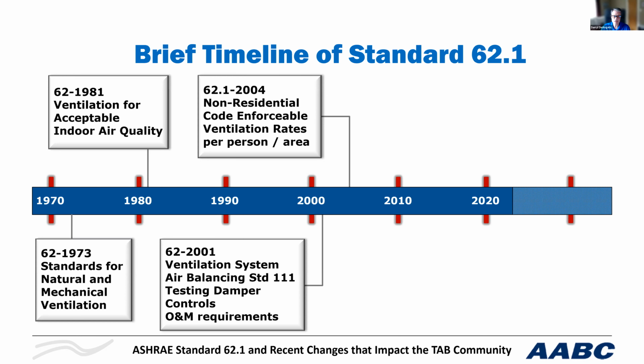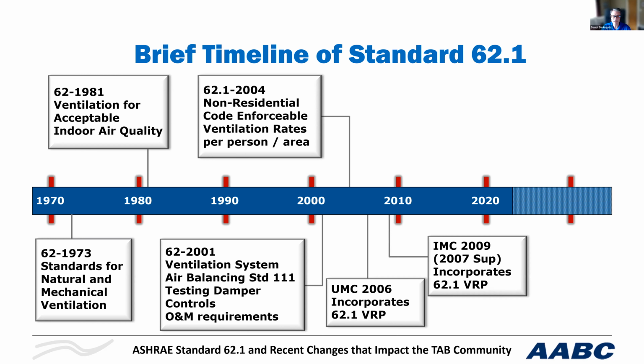And one of the big changes is the ventilation rates. Instead of a single rate, it was broken up into a ventilation per person, per occupant, and a ventilation per building or area or per the space. This was basically important, so every space is not treated the same. Some spaces need more ventilation than other spaces because of off-gassing in that space. So there's some advantages to that. And in 2006, it was adopted into the Uniform Mechanical Code, and then through a 2007 supplement, and through the issue of the 2009 International Mechanical Code, it was now incorporating the ventilation rate procedure. So this has kept the code ventilation requirements and ASHRAE 62 closely aligned.